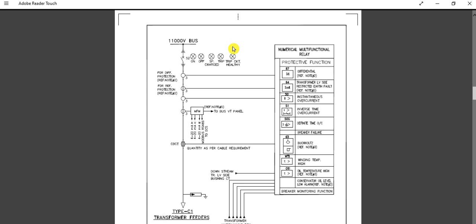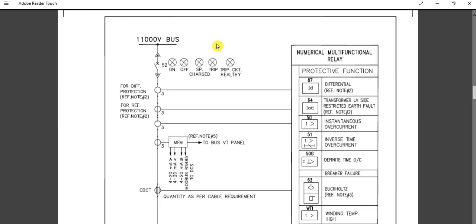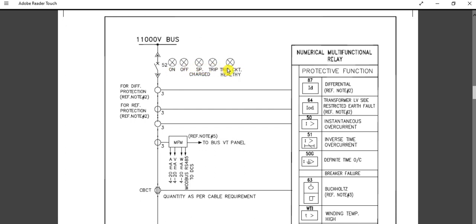As you can see based on the scheme, this is the 52 circuit breaker — a withdrawal or draw-out type circuit breaker, as I explained in my previous video. These are the breaker status signals: breaker on, breaker off, trip, and trip circuit healthy. There may be more or fewer signals depending on the project specification requirements.